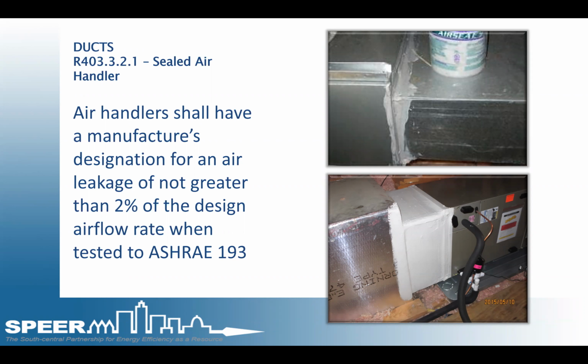A common duct testing target on a 3-ton system would be somewhere in the neighborhood of 46 CFM, depending on the square footage of the house. So out of that 46, if 24 of it is allowed by code for cabinet leakage, that only leaves 22 CFM to leak for the entire duct system. That's why it's very important that duct systems be mastic, panduit, strapped and sealed to the best ability of the contractor. Any of us that has done duct testing can attest that a 22 is a very difficult target.